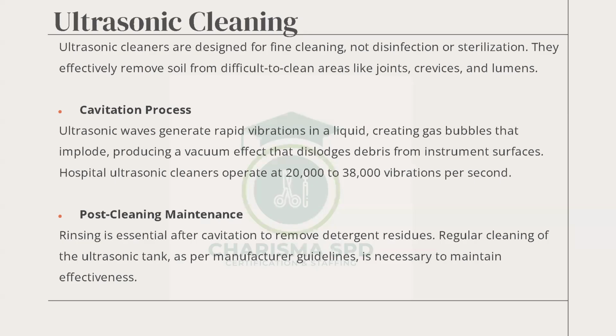The post-cleaning maintenance. Rinsing is essential, and this is one of the questions that always come. They ask you, is it essential to rinse something after it's been cleaned in the ultrasonic machine? Rinsing is essential after cavitation to remove detergent residue. That is a bonus question to you. Regular cleaning of the ultrasonic tank, as per manufacturer guidelines, is necessary to maintain effectiveness. That is a machine that, if you use it, it needs regular cleaning.